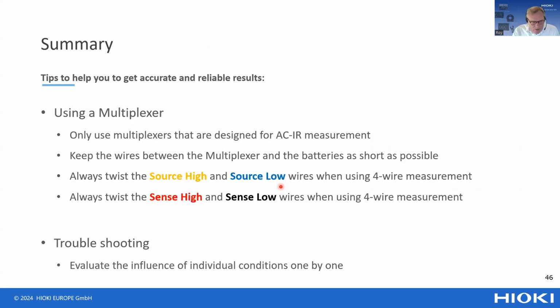When you decide to use a multiplexer in the production line, only use one that is designed for ACIR measurement. Keep the wires between the multiplexer and the batteries as short as possible, and as with a direct connection, always twist the source high and source low wires, and the sense high and sense low wires.